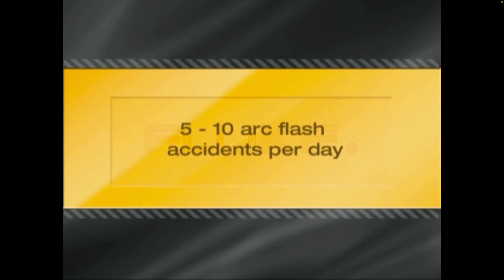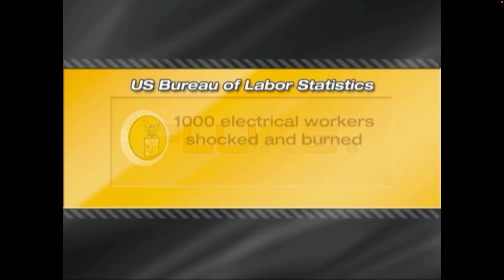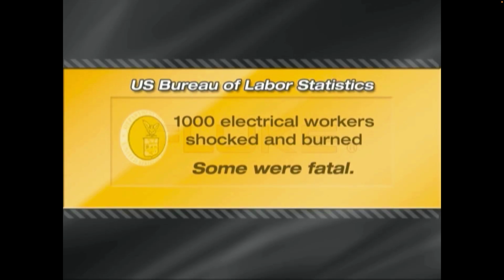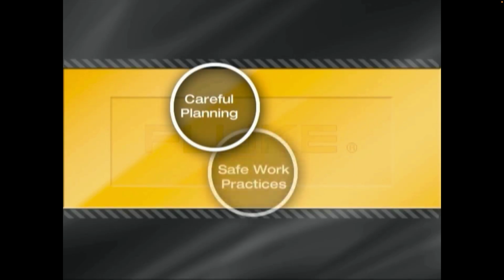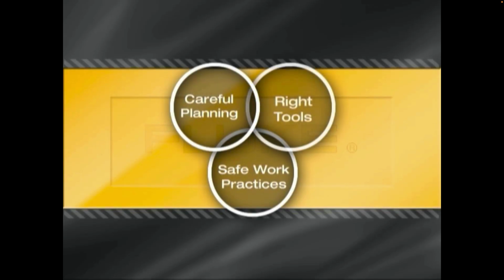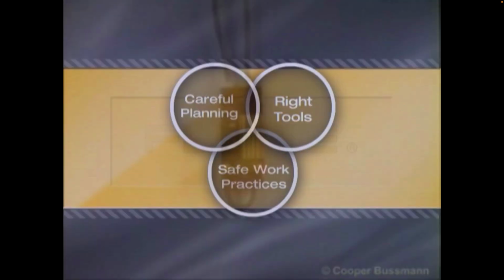Industry sources estimate that in the U.S., 5 to 10 arc flash accidents occur each day. The U.S. Bureau of Labor reports that in one recent year, 1,000 electrical workers suffered shocks and burns, some fatal. It is estimated that 50% of these injuries are related to arc flash. This percentage could be dramatically reduced if technicians utilize the combination of careful planning, correct safe work practices, and use of the right tools. Here is an actual arc flash.